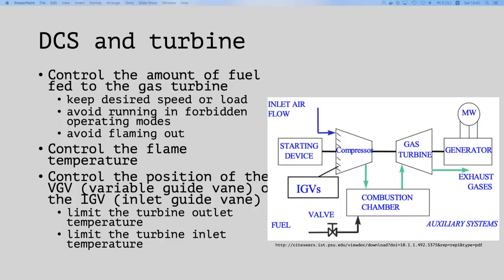For example, if we wanted to answer how we would regulate the output in megawatts of our power plant, we would need to control basically three things. Again, we are oversimplifying here. This is an example for a gas turbine. We would need to regulate how much gas we put inside the combustion chamber, control the flame temperature, and control the air intake into the turbine. Basically three things controlled by simple PLCs in the whole system, and you would be able to change, for example, 100 megawatts to 150 megawatts based on these settings.